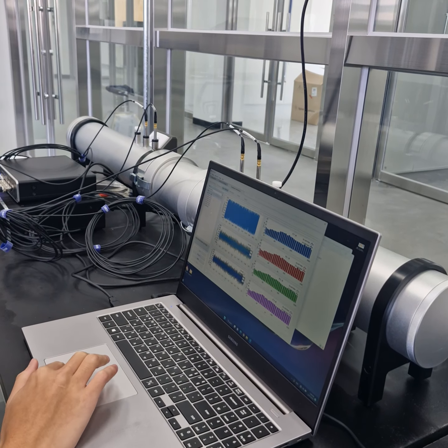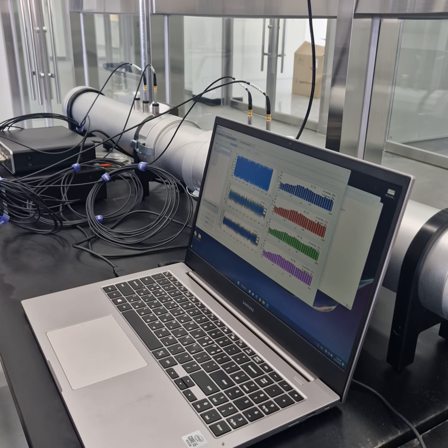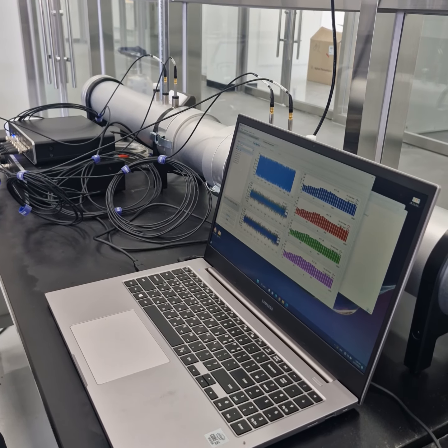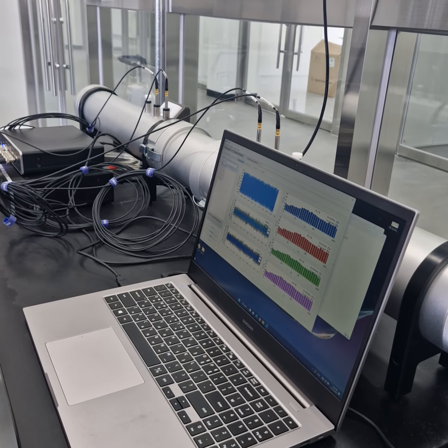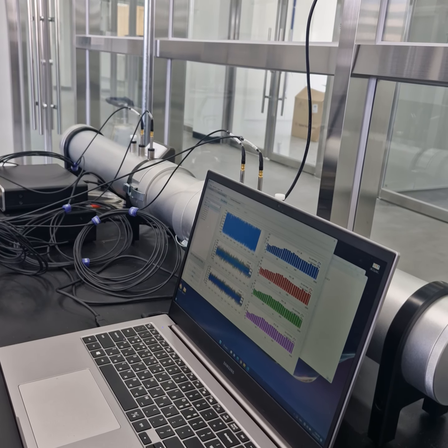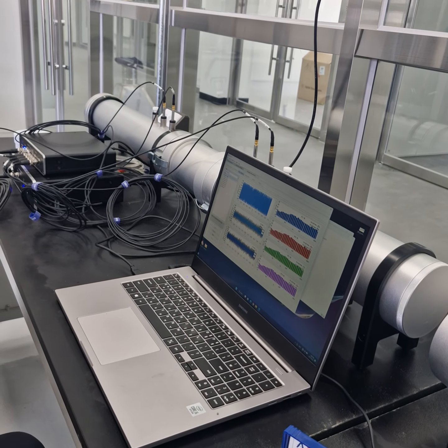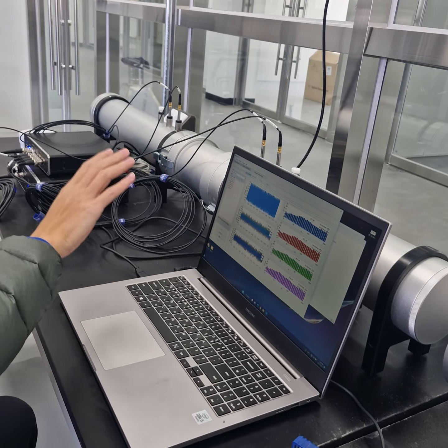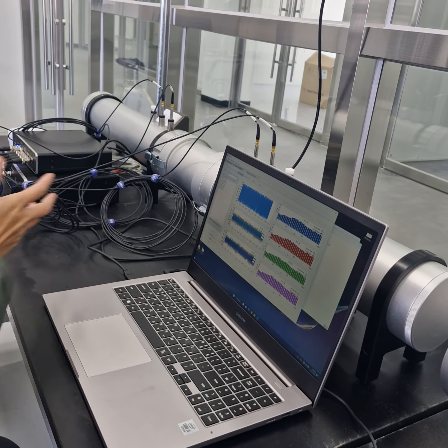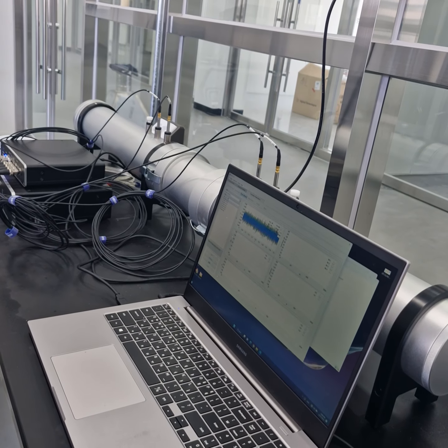Okay. So when we do calibration, we don't need to make a sound. Just like wow here. Actually, because inside the tube, the noise is far higher than our speaking sound. So actually, it doesn't matter. Yeah. This is the only equipment that does not need to be put in the anechoic chamber. That's also a convenient thing. Speaking doesn't matter that much, I would say.